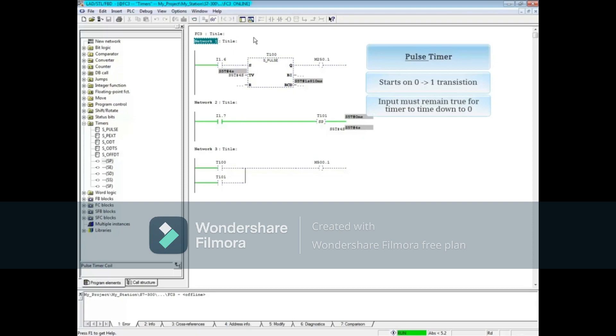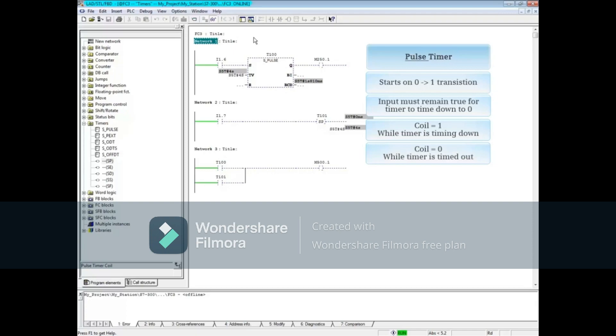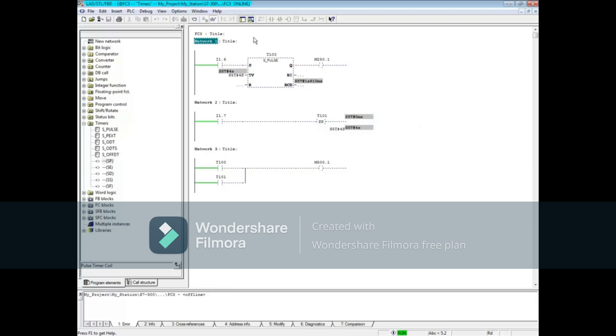The input must remain true for the timer to time to 0. The coil is 1 or true while the timer is timing down, and the coil is 0 when the timer is timed out. Each time the input transitions from 0 to 1, the timer automatically restarts.